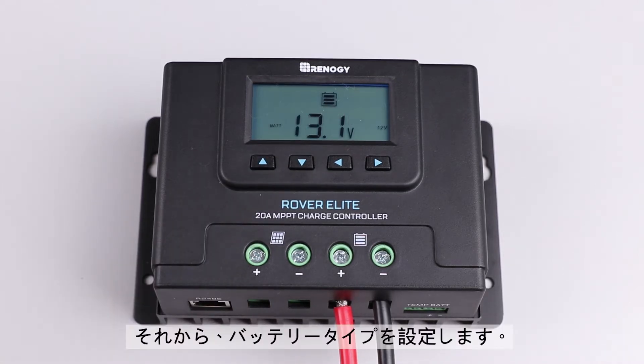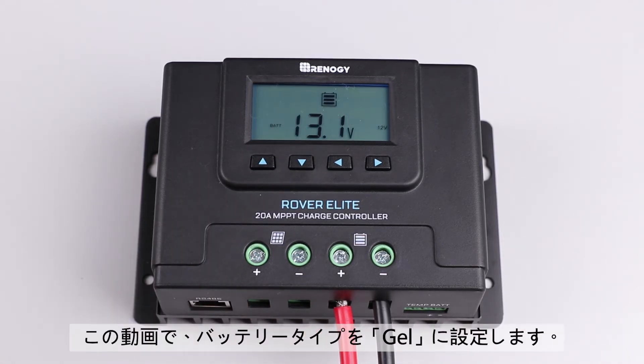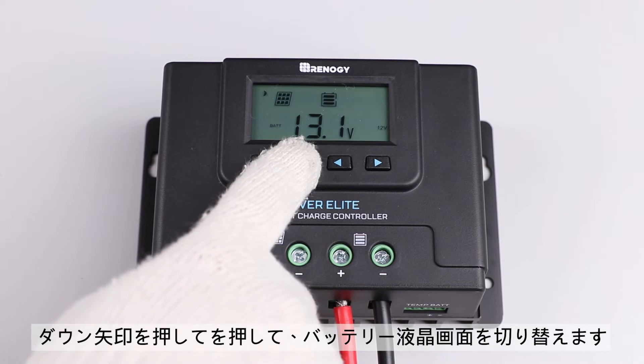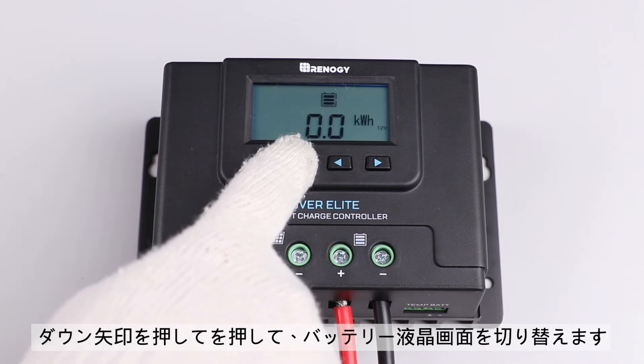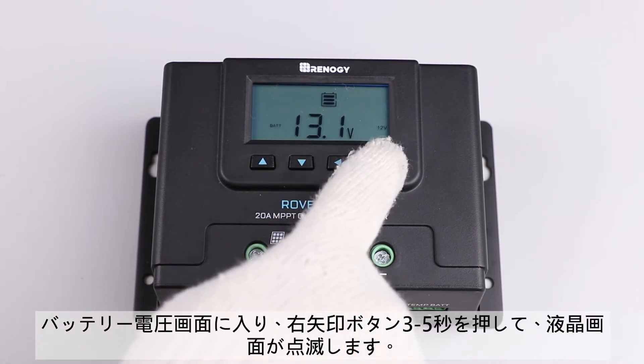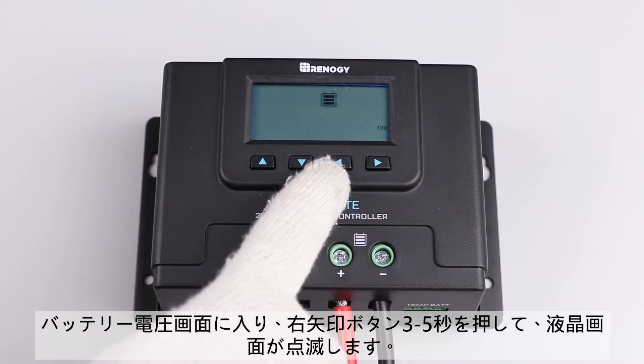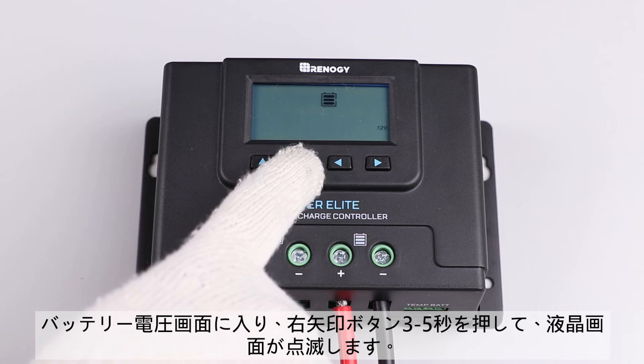The next step is to set the battery type. In this video, we will be setting it to Gel. To change the battery type, switch to the battery voltage screen by using the down button. After reaching this screen, press the right arrow button for approximately three to five seconds until the screen flashes the current battery type.